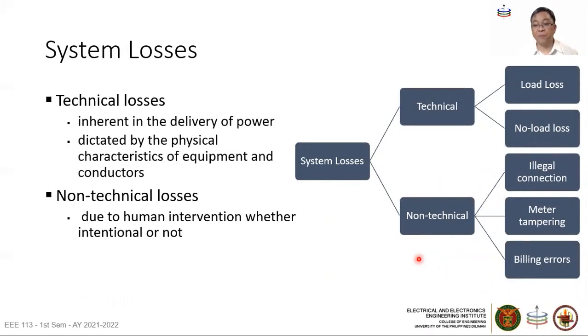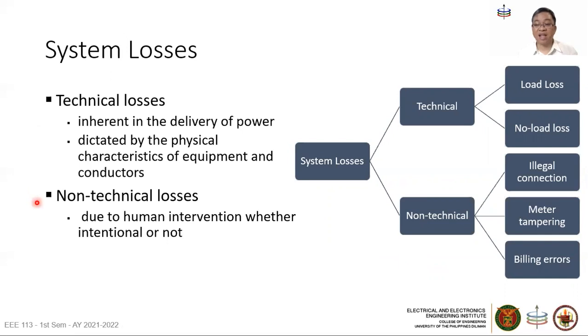Another concern in delivering power is the reality of system losses. The utility tries to quantify and manage losses — initially losses will be reduced, but eventually maintained at a very low but reasonable level. We differentiate between technical losses and non-technical losses. Technical losses are inherent in the delivery of power, dictated by the physics of the devices. For example, when current flows through a wire, the resistance converts some electrical power to heat. Unless we use superconductors, losses can be a few percent of delivered power.